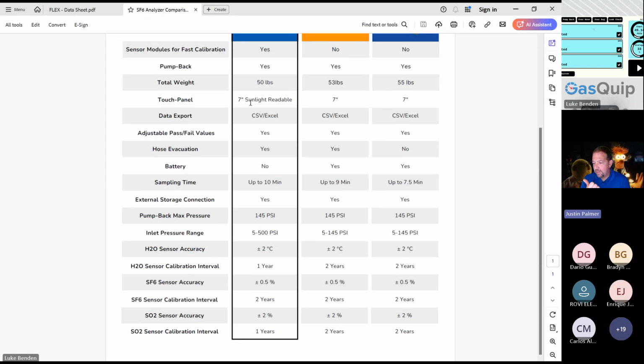The purity sensors on all the devices, where they use infrared or velocity of sound, are all plus or minus half a percent. So that's going to be basically the same for everybody. And the SO2 modules, even if you buy the most expensive analyzer on Earth right now, it's still an electrochemical sensor, and the accuracy is still the same. And they still degrade in the same manner. If you want higher accuracy on your SO2 sensor, you have to decrease the range of it. You can do them 0 to 100 versus 0 to 500, and you get a higher resolution.